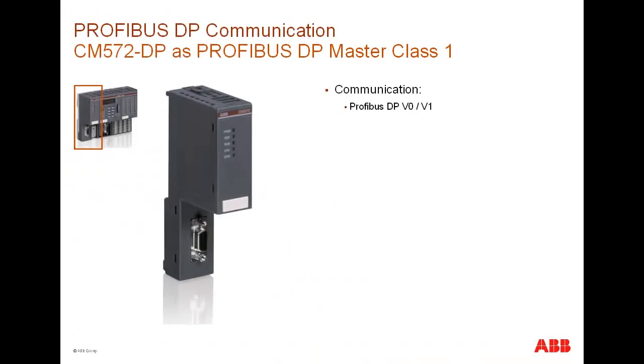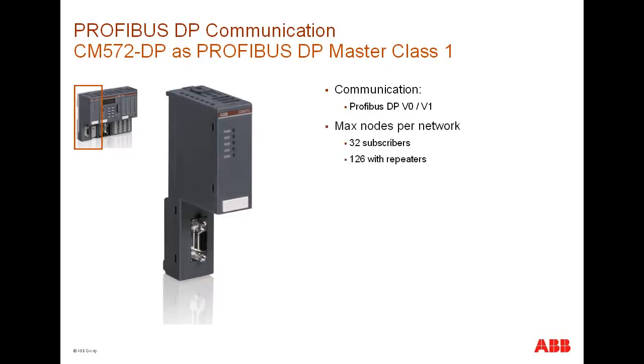The CM572 DP master that we discuss in this example supports both DPV0 and DPV1 communication types. This means it could support both cyclic and acyclic data transfer between the master and slaves. Up to 32 stations or nodes including one master and 31 slaves could be operated in one PROFIBUS segment.